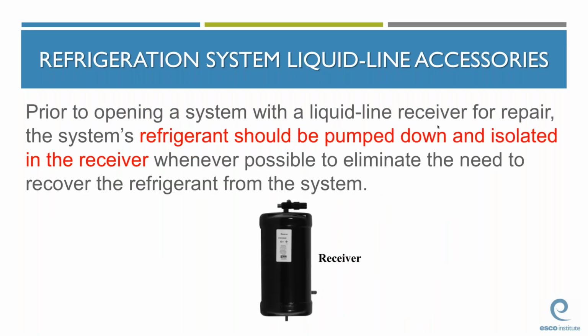If the system being serviced has a refrigerant receiver, the system should be pumped down so the refrigerant is stored in the receiver and condenser coil whenever possible. Be sure to explain this to your students so they'll understand the process of system pump down as well as when it can and can't be done. And this will depend on system configuration and also the repairs being made to the system.